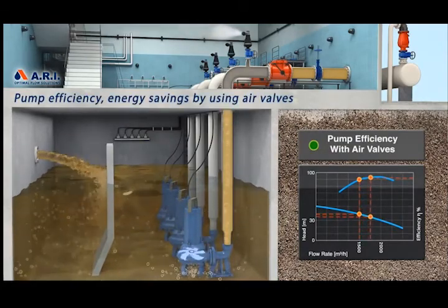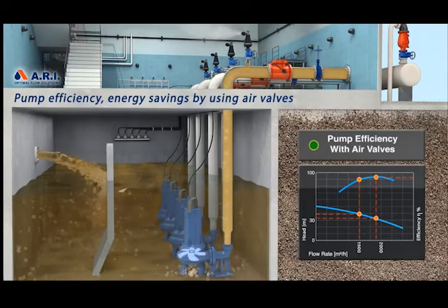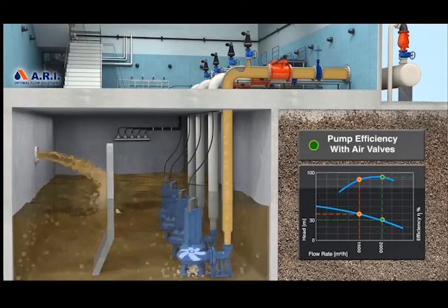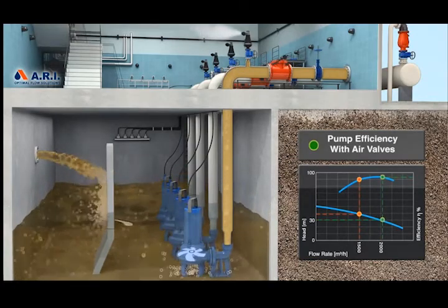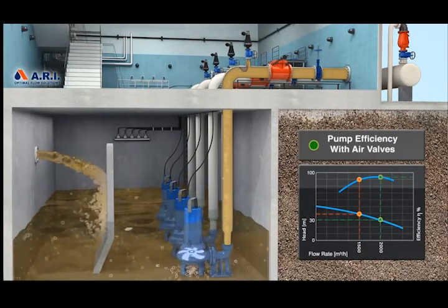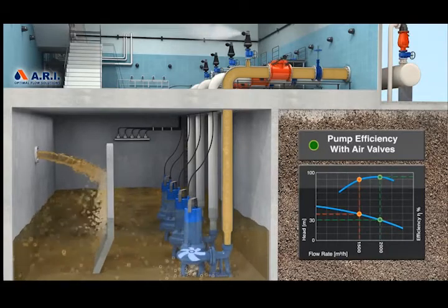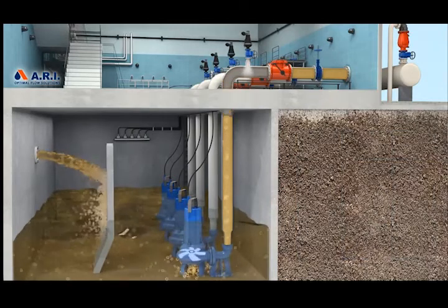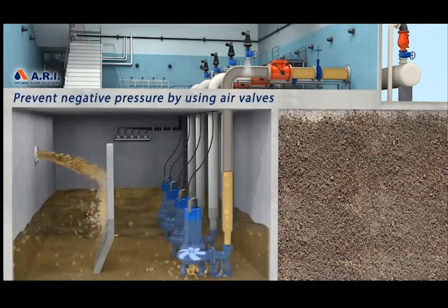In our case now, we've gradually discharged the air efficiently, and we see our pump curve has shifted to a much larger flow, compared to that initial restriction, and lower head. So now, in contrast to that initial case, we have full system capacity and efficiency.